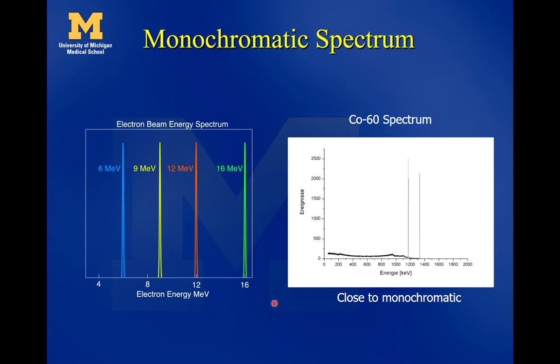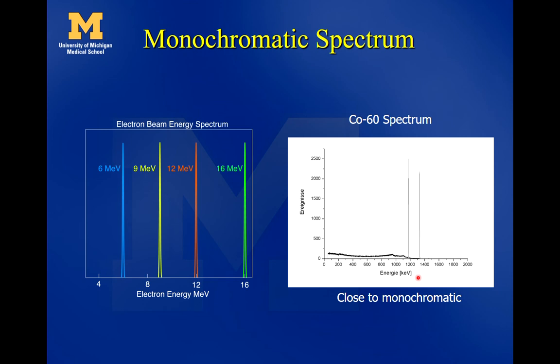Examples of monoenergetic beams include the electron beams in our linacs at 6, 9, 12, and 16 MeV — these thin little Gaussians show the spectrum of electrons coming out, narrowly bunched right around each energy. Cobalt-60 is also nearly monoenergetic: it has gamma rays coming from its nucleus, dominated by two main peaks around 1.2 MeV. These are examples of monoenergetic x-rays, in contrast to the polychromatic spectrum from an x-ray tube.